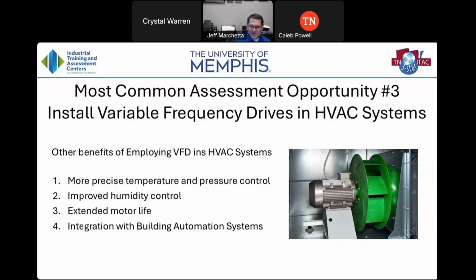They also extend motor life. Starts and stops on motors are just not very good for motors, so one solution is soft starts. VFDs can actually act as soft starts for you, so if it's a variable system, you don't need the soft start - you can use the VFD instead. Extending motor life is important, and VFDs are easily integratable with a building automation system if you have one or intend to purchase one.